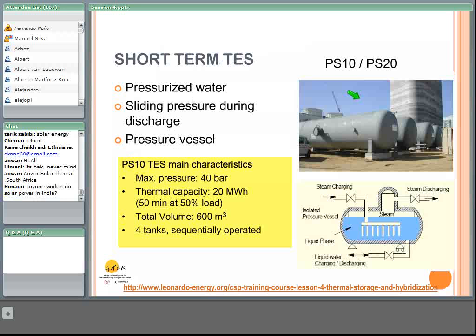The maximum pressure is 40 bar. It's close to the pressure of the steam at the receiver. The thermal capacity is 20 megawatt hours, and that's equivalent to 50 minutes at 50% load of the turbine, and the total volume of the tanks is 600 cubic meters. The system is made of 4 tanks, which are sequentially operated. Here you can see a drawing of one of these systems with steam charging and steam discharging.